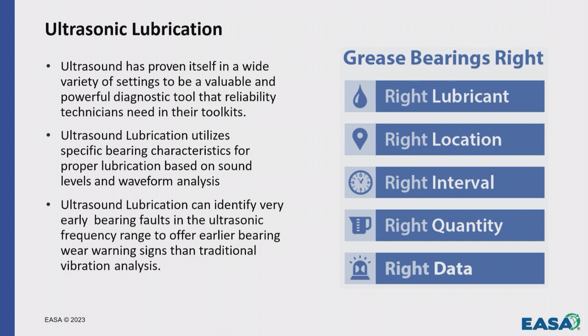There's a couple different manufacturers out there that make the tools. There's some simpler ones, there's some more advanced ones. The particular one we use has a little bit more advanced functionality with regards to being able to analyze the waveform and understanding the spectral data coming out of that ultrasound data. So that gives you a really added benefit of understanding when bearings are starting to develop fault frequencies at the high frequency level of ultrasound. So it should give you warning signs before the vibe techs can even pick this up. So it's really a proactive technology that helps the customer out and helps with unplanned downtime.